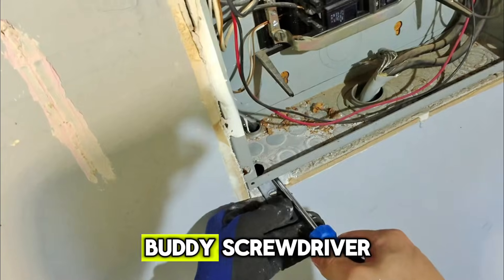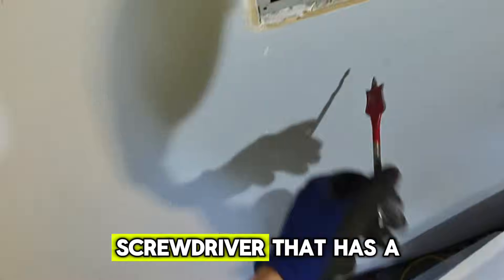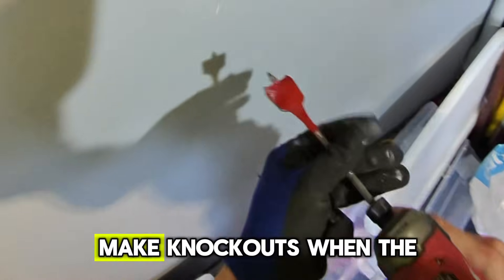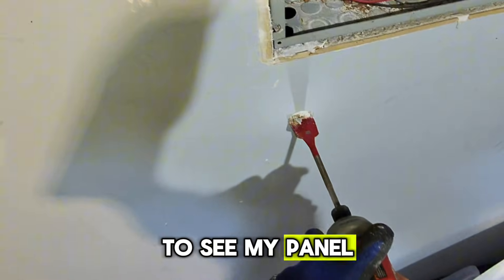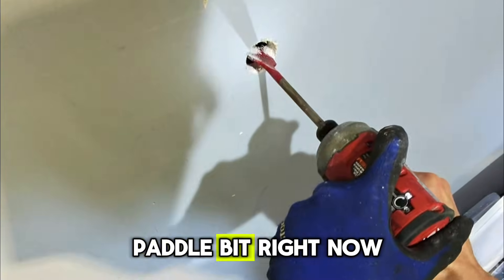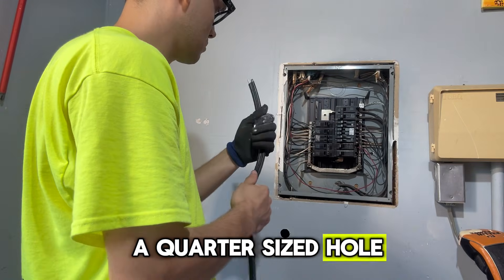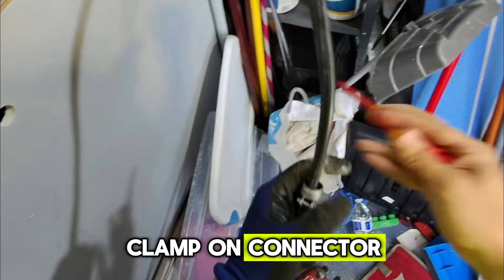Right now I'm currently using a panel buddy screwdriver. A panel buddy screwdriver is a specialty screwdriver that has a curved tip that allows you to make knockouts when the panel is flush mounted. I highly recommend it. I was able to sleeve my panel buddy under the panel, got a half inch knockout, and I'm using my paddle bit right now to make a quarter sized hole — just enough to fit my half inch Romex connector clamp-on connector.